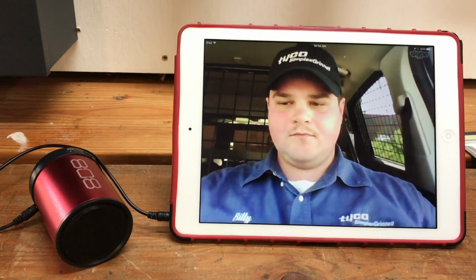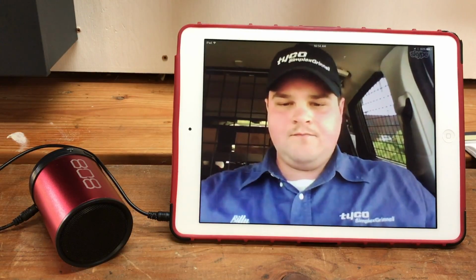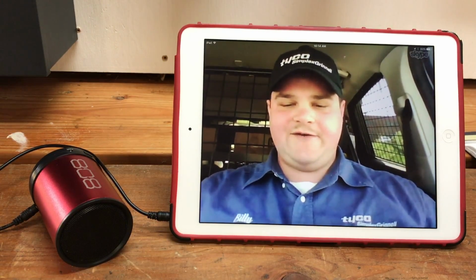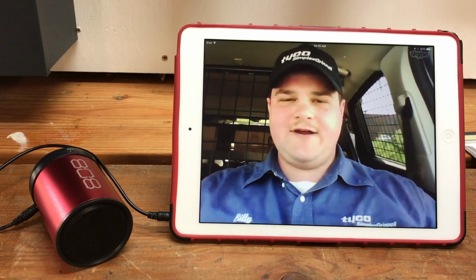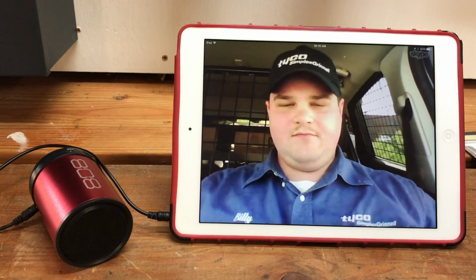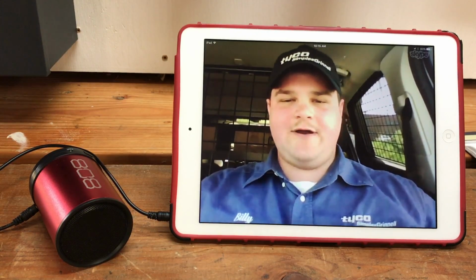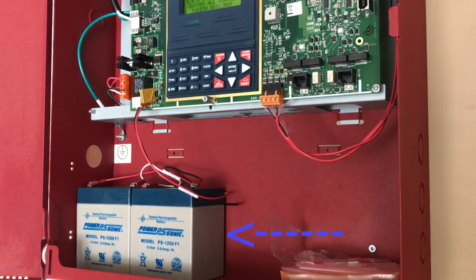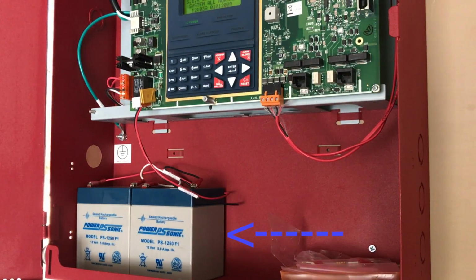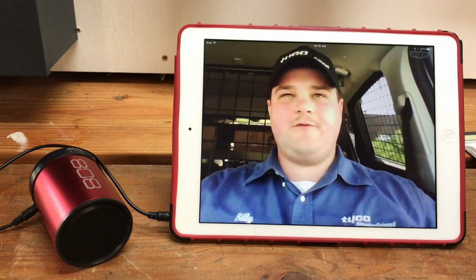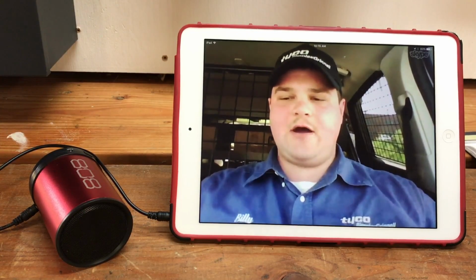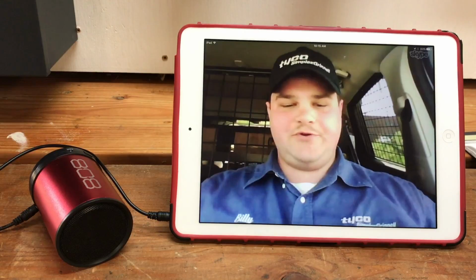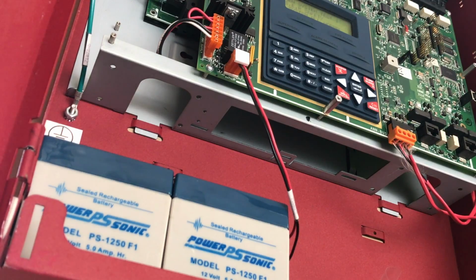Do fire alarms work with no power? Yes, they do. They have what you call sealed lead-acid batteries, which are basically one step down from car batteries, and they are located at the fire alarm panel. Per NFPA, they should be able to supply the system with power for at least 24 hours after a power outage, and they are rechargeable, so they recharge once the power comes back on.